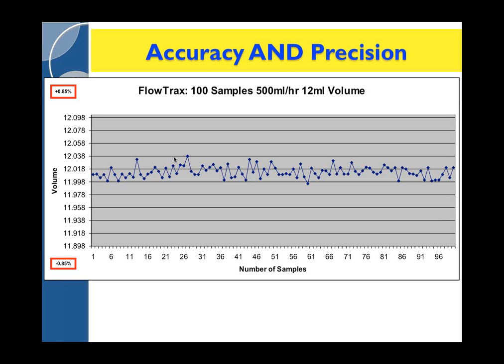Just a quick snapshot of the precision of the Trax. We've talked about its accuracy, but this is a 100-sample test performed on the Trax using one of our proprietary test fixtures that's capable of a 0.25% accuracy. And you can see at the top and bottom of the scale on this graph the limits that we put on our test fixtures and our Trax test procedures. It has to hit plus or minus 0.85%, for example, at 500 milliliters per hour. So you can see the precision of the Trax measurement is much greater than the accuracy spec.